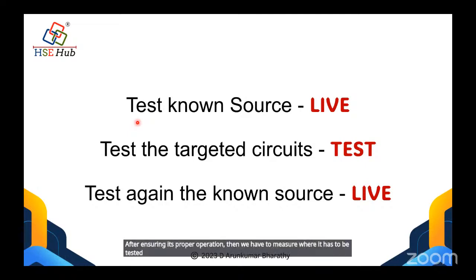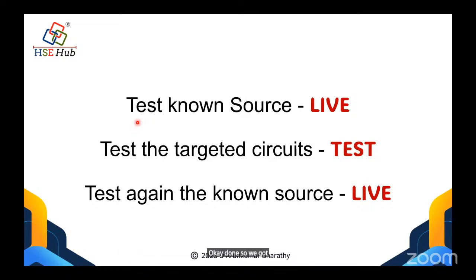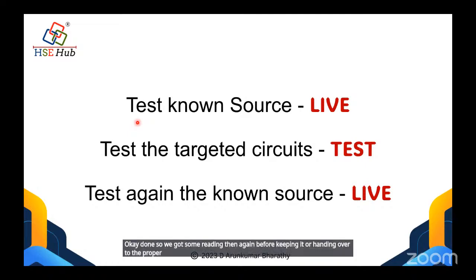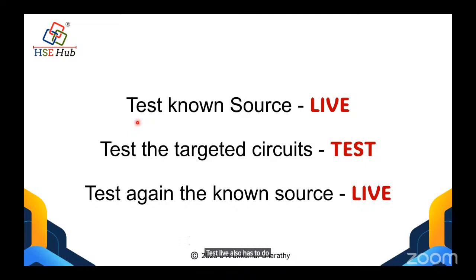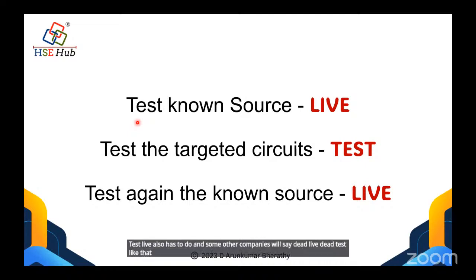That is a live measurement. That is actually the measurement. Okay, done. So we got some reading. Then again, before keeping it or handing it over to the stores or wherever, we have to check with the reference voltage again. We have to ensure that yes, now also my instrument is fit to measure. So the live test also has to be done. And some other companies will say dead-live-dead test like that. But this is very important to ensure my instrument is performing well or not.